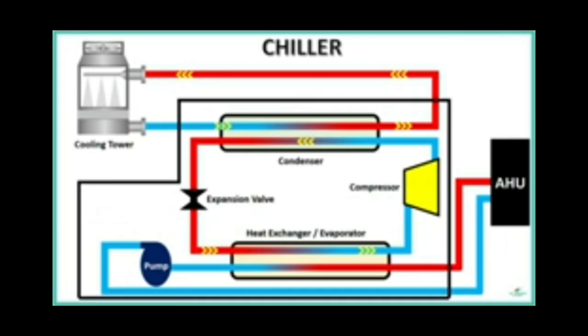The low-pressure chilled refrigerant flowing inside the evaporator cools the hot water from the AHU and produces chilled water. The chilled water is pumped back to the AHU. This cycle repeats.